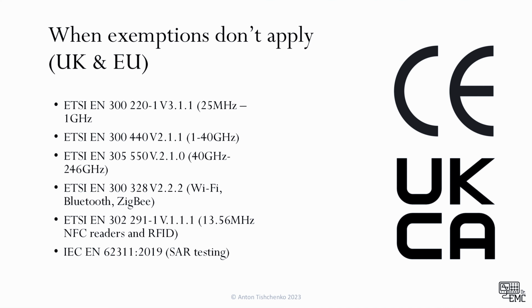Finally, if it's a device such as a mobile phone and it is to be used within 30 centimeters in its normal function from a human body or head, then specific absorption rate testing will also apply, regulated by EN 62311/2019. This test is particularly difficult to perform and is extremely expensive, as it requires a model of a human body placed inside an anechoic chamber, and the performance of radio equipment needs to be evaluated in a sphere.